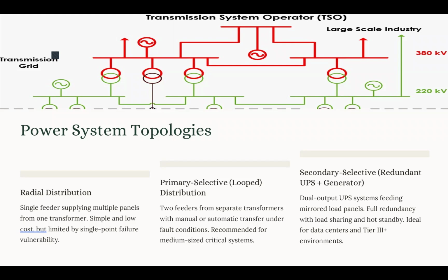The third topology is the secondary selective distribution. Now, it's a fully redundant dual power source, mostly operating in parallel or hot standby. It has the highest reliability, like Tier 3+ or even Tier 4 data center compliance. It is automatic. It instantaneously transfers during a failure of one source, and it is normally used in mission-critical, sensitive electronic equipment environments like data centers, surgical suites, or telecom hubs.